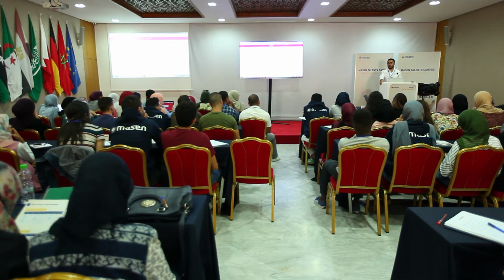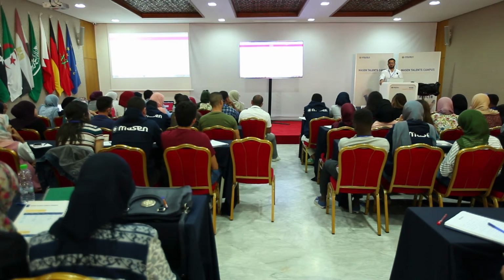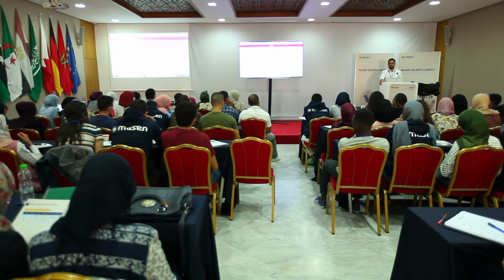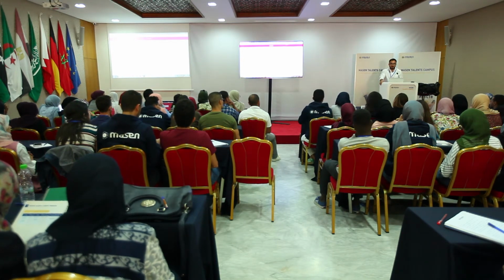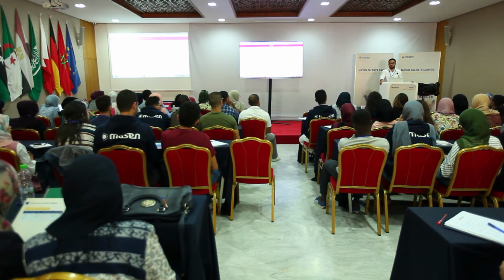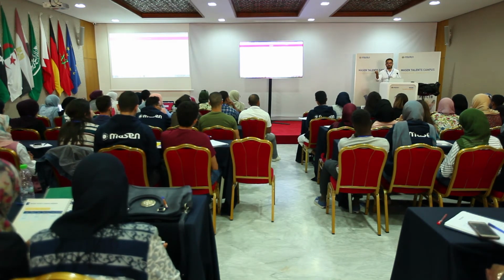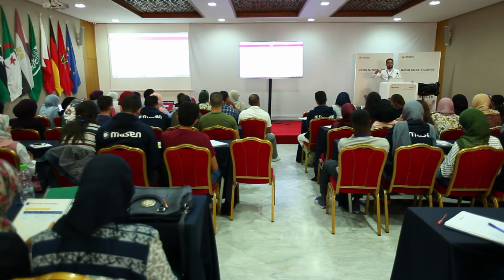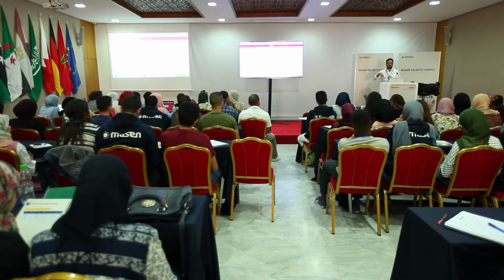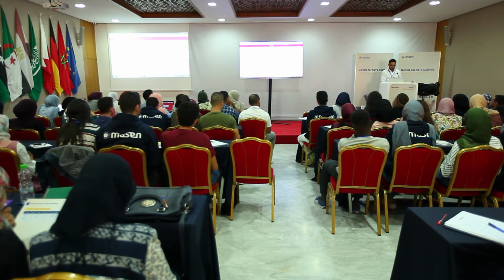But then the reason comes back to what we were saying before. It's not only the technical issues, it's costs. It's more costly today to put in a PCM or a latent heat system. Also, we don't have the know-how yet to build such a system. We don't know what will happen in terms of the lifetime and the degradation of a system that is going from liquid to solid all the time, whereas for the liquid ones, we know. So that's where the CSP industry is going. Of course, we're moving from steam cycles to gas cycles, hopefully, and from sensible heat to latent heat, all of this. But today, it's not there yet. It's costly, and we don't know technically if they are proven.